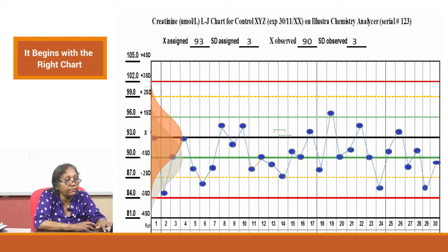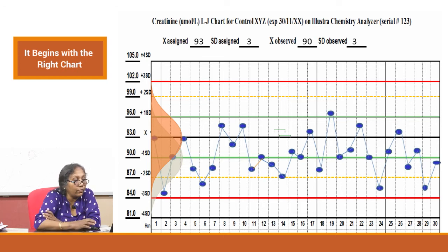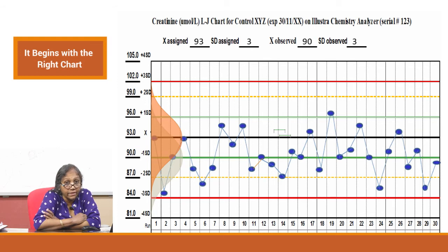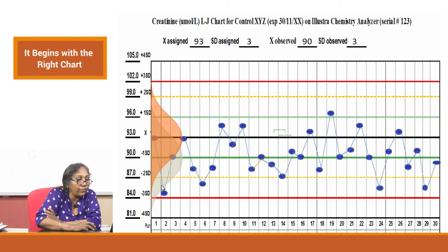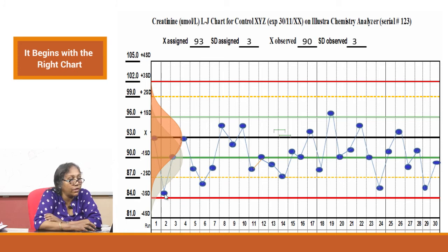If you look with 90 as the mean, there are no rejections that should happen — these are all good runs. But with 93 as the assigned mean, these appear as 1:2S warnings. Conversely, a point that should be a 1:2S warning using the correct mean of 90 goes unnoticed because referenced to 93 it looks like a normal run, creating false acceptance.